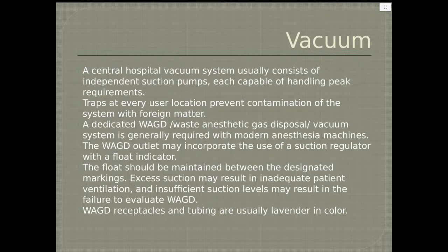Excess suction may result in inadequate patient ventilation, and insufficient suction levels might result in failure to evacuate the waste anesthetic gas disposal. The receptacles and tubing are usually lavender in color for the vacuum.